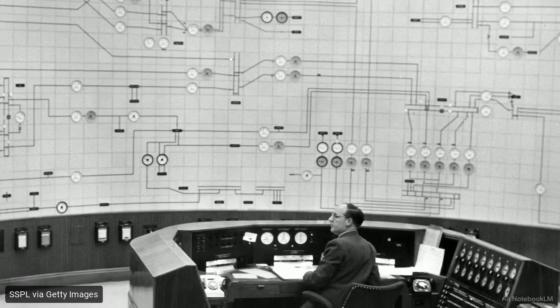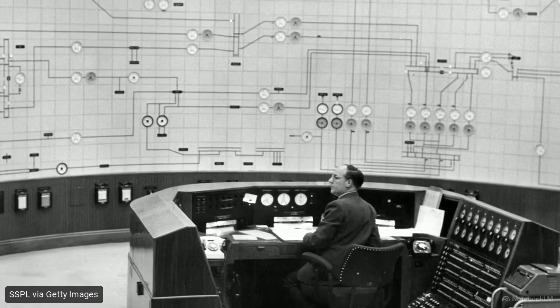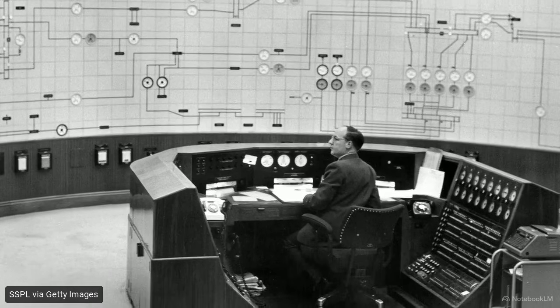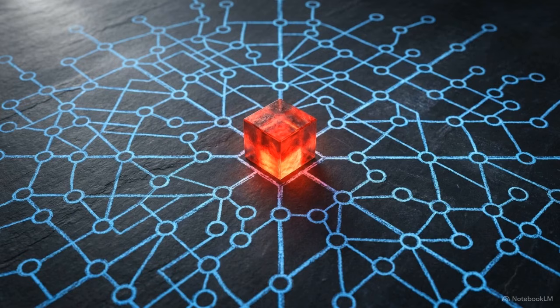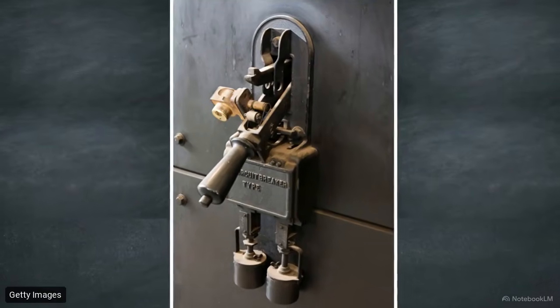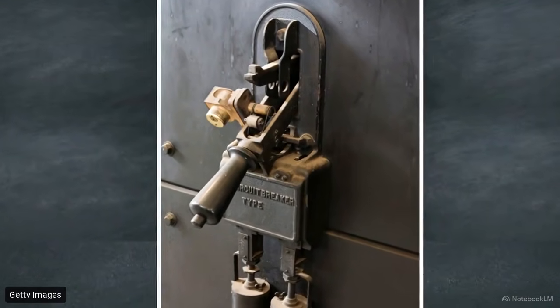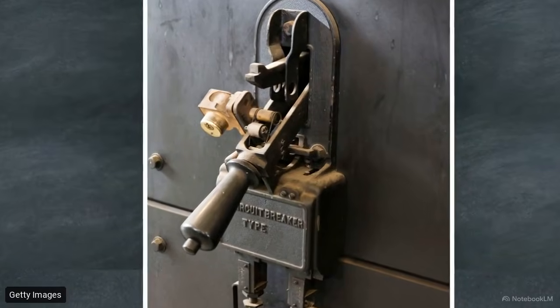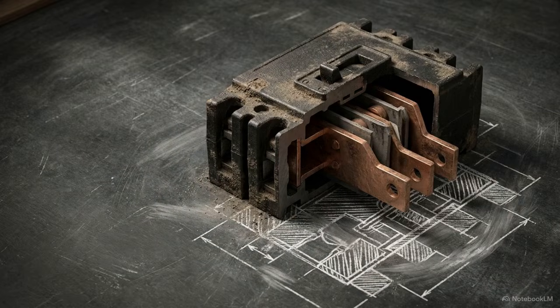Surviving these physical forces requires managing them across a grid that spans thousands of miles. Operators monitor the network continuously, but human reflexes are far too slow to manually stop an event that unfolds in milliseconds. That responsibility falls to the circuit breaker. It operates as the ultimate line of defense, a heavy, mechanical device specifically engineered to endure the initial shockwave of the fault and extinguish the plasma arc.